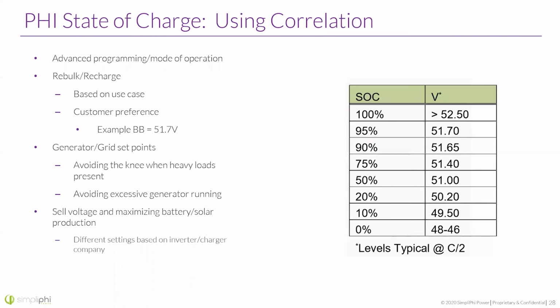It can also help with generator and grid set points — avoiding excessive generator running, understanding how low you can set your generator or grid threshold to start charging, and even avoiding the knee we talked about earlier. Another big use for these correlations is sell voltage: understanding where the battery is at 100% helps set that sell voltage so it only sells off PV. Settings can differ from inverter company to company, but knowing this correlation helps ensure your customer isn't losing that extra excess sell while keeping their battery nice and charged.